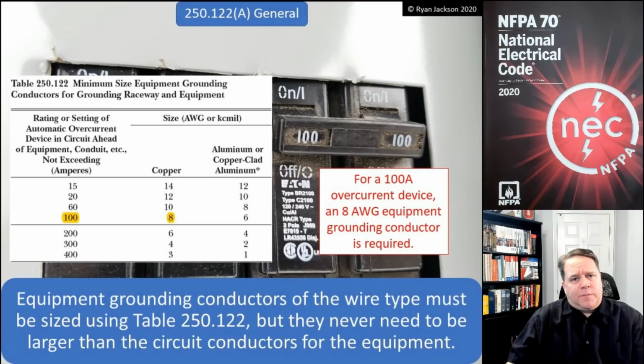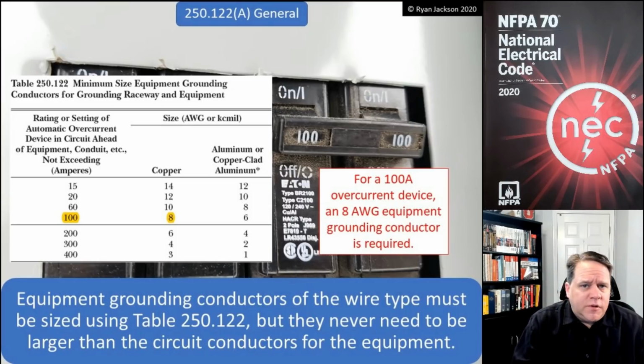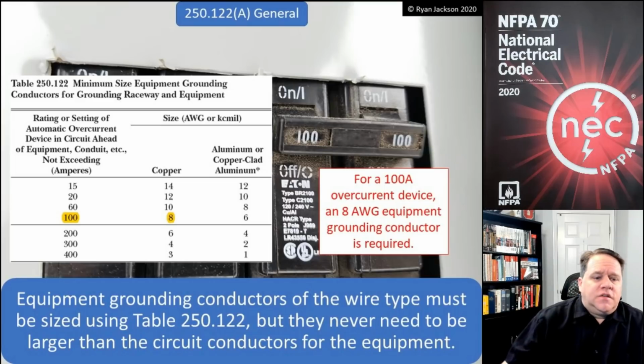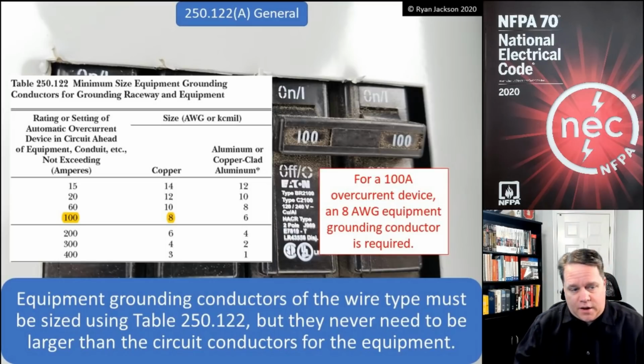So for normal applications, 250.122(A) says that the equipment grounding conductors of the wire type must be sized using Table 250.122, but they never need to be larger than the circuit conductors for the equipment. All right, pretty simple, to be perfectly honest.